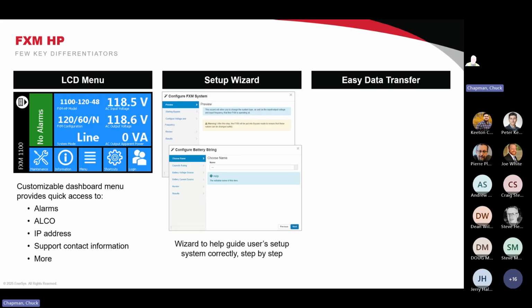There are setup wizards that walk you through configuring the FXM system for operation. It's not like you have to go through 30 screens for a particular item—you go through one screen, click next, go to the next screen, and eventually finish configuring it, usually in just a few seconds. I set up its operational mode and frequency, then go into the batteries, choose the battery, maybe set the battery name and string name, then choose the battery manufacturer and model and accept the predefined settings. It's really quick to do the setup wizard.